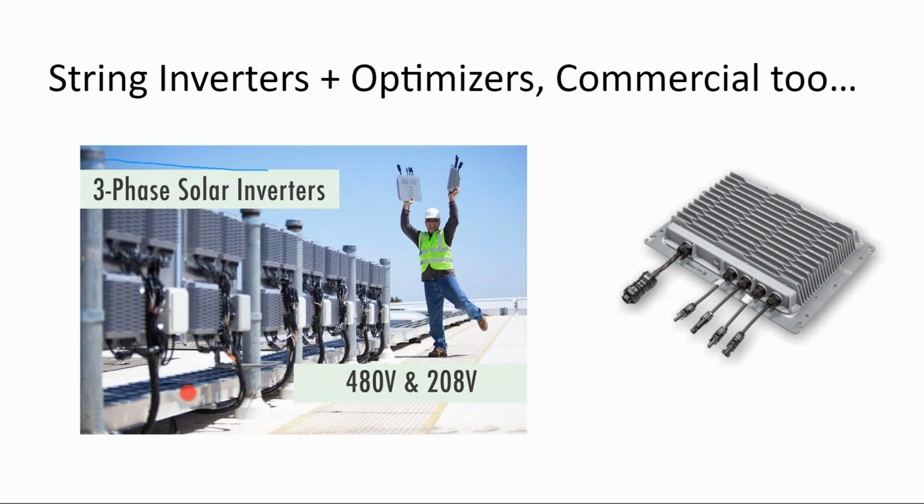And for anything, it's as much to make sure that the cables are kept up off the roof deck as much as possible. So I know in the Solar City circumstance, they were not doing much maintenance on the arrays. Not giving it an annual visual inspection.